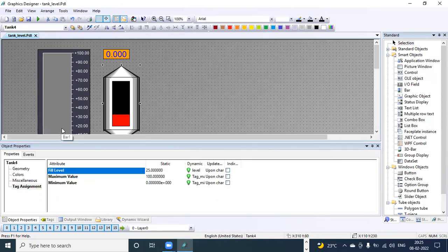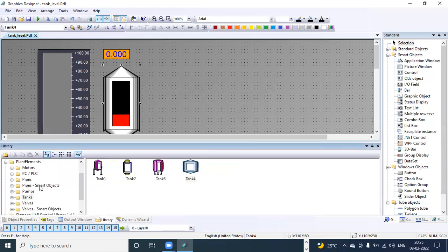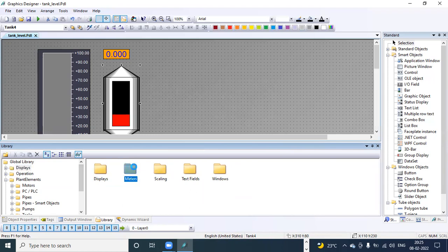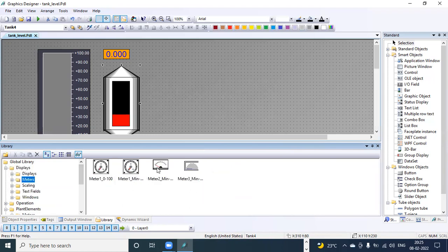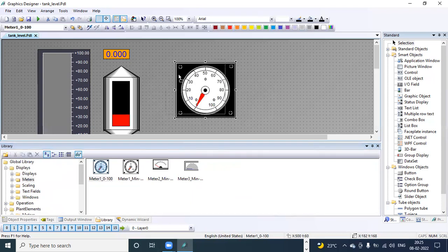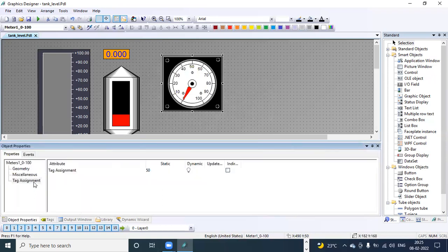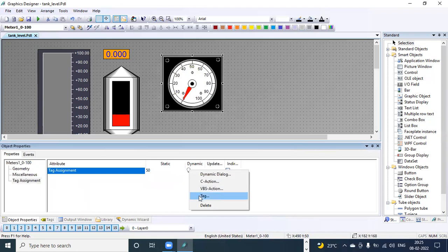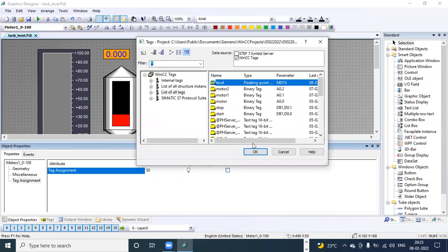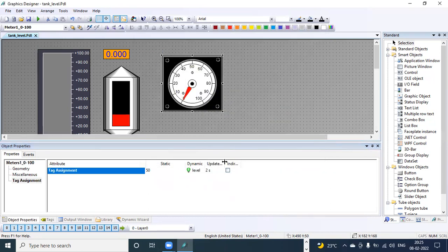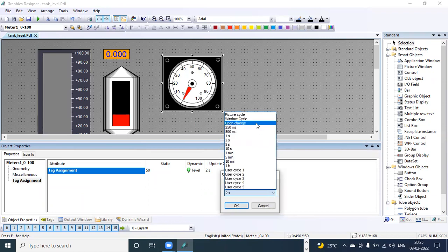Under the Library there is also a Display section where you can see meters — different meters from 0 to 100 are available. Simply drag and drop the meter into the graphic. Then select object properties. For displaying the value go to tag assignment — for analog you give the tag directly, no need to go through the dynamic dialogue. Set the update cycle by double-clicking — select "upon change".